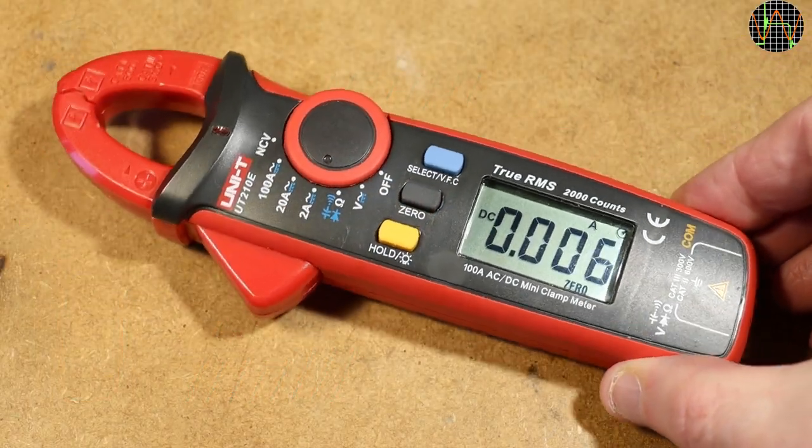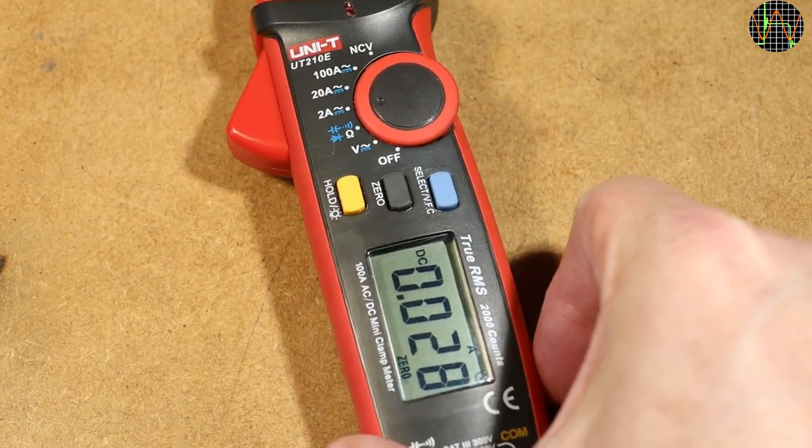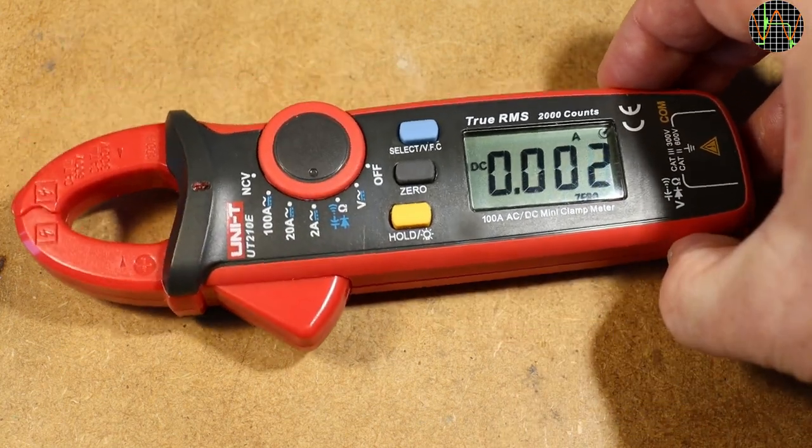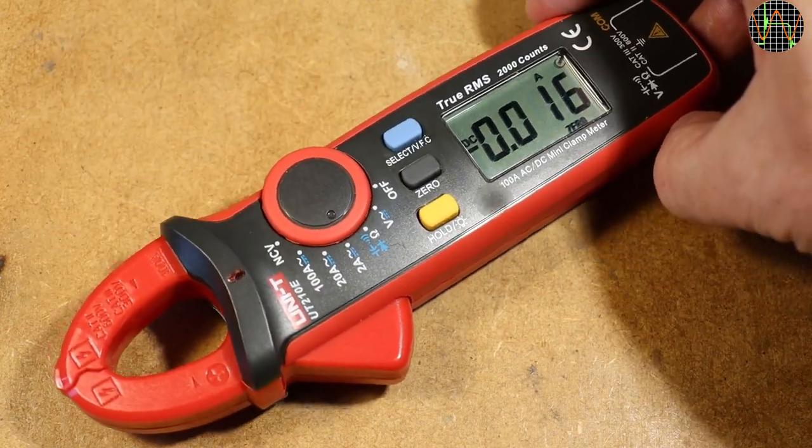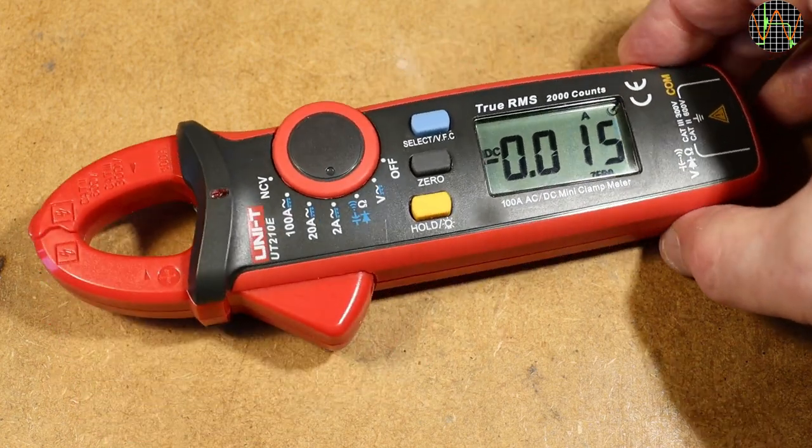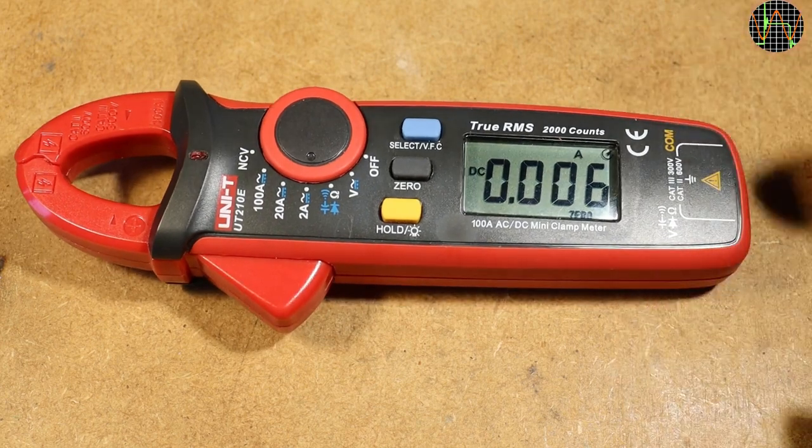Before covering the two procedures to adjust the trim pots in your UT-210E if your offsets are very high, I want to quickly go over how to measure currents correctly because some of your problems may actually originate from there, and if so, you may avoid having to touch the trim pots in the first place which is definitely the best solution.